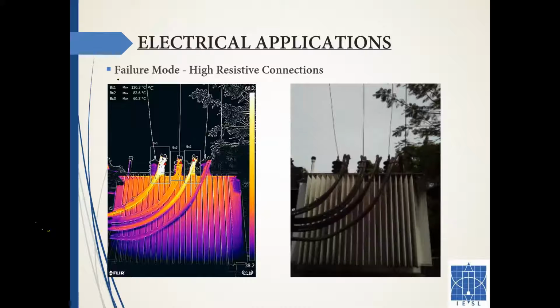These values you need to compare with your cable insulation. The PVC and cross-linked polyethylene insulations are designed to withstand a maximum of about 90 degrees C, whereas here you have almost 130, around 82 degrees on the middle one, and the last one is also 60 degrees. You can see the burn marks here if you look closely. This is potentially really dangerous.